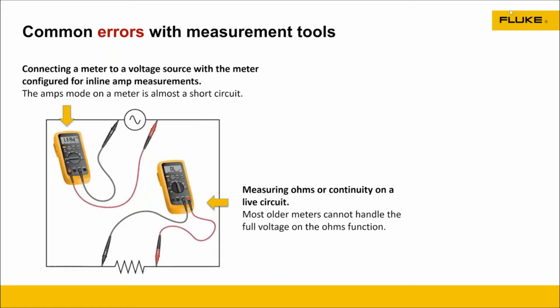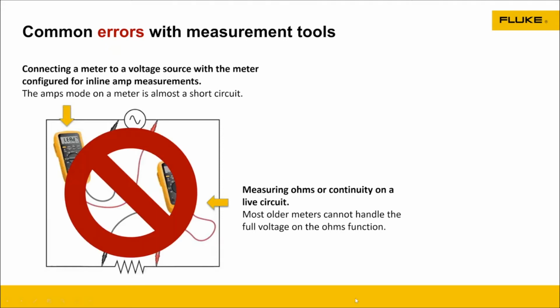But typically when you're measuring ohms, continuity, voltage, you've got the test leads in the right position. That's kind of a key win. But again, knowing your meter and knowing where that is, that's crucial. Older meters can't handle that type of voltage in an ohms position. So know what your meter is.